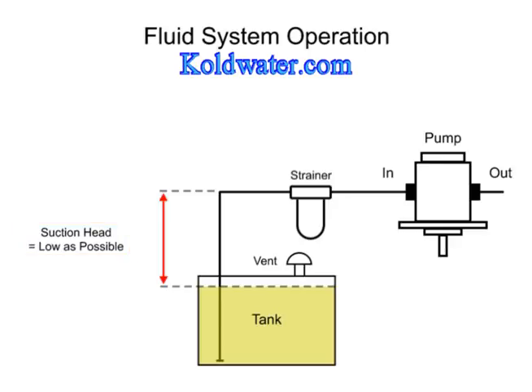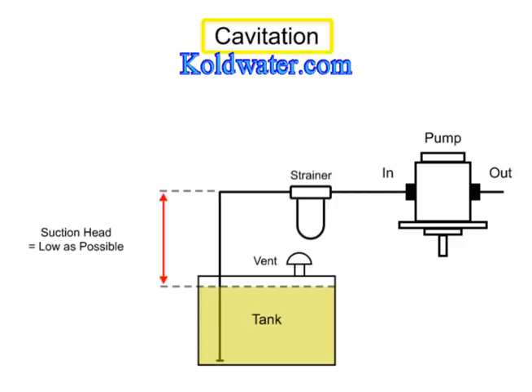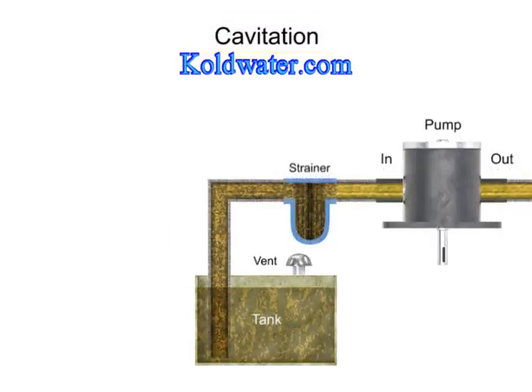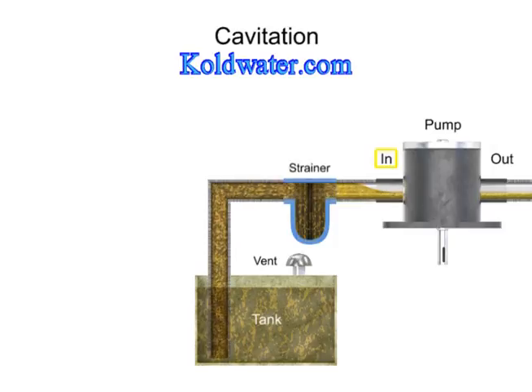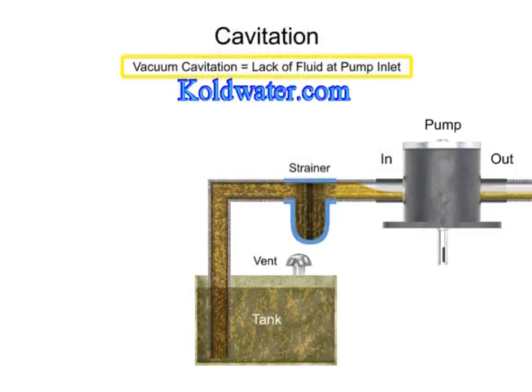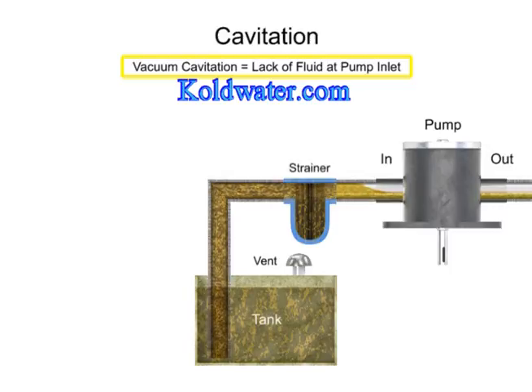Several issues may occur if enough fluid does not flow to the pump inlet. One such scenario is called cavitation. The most common form of cavitation occurs when the inlet fluid is not entirely filling the cavities which open up for it on the pump inlet. This type of cavitation is called vacuum cavitation, a condition commonly known as starving the pump, because not enough fluid makes it to the inlet.